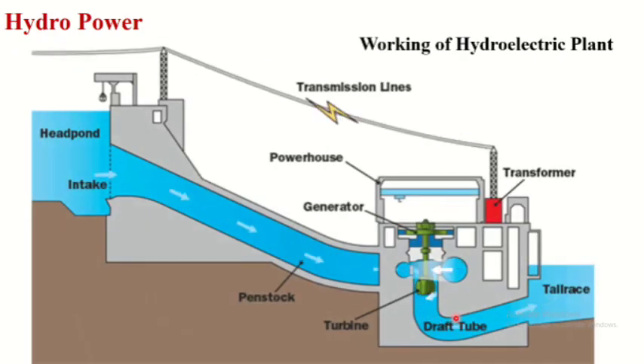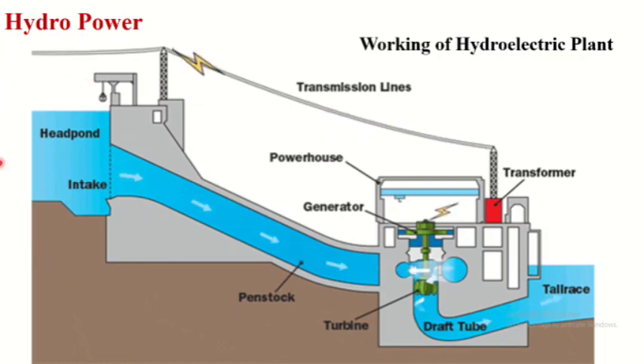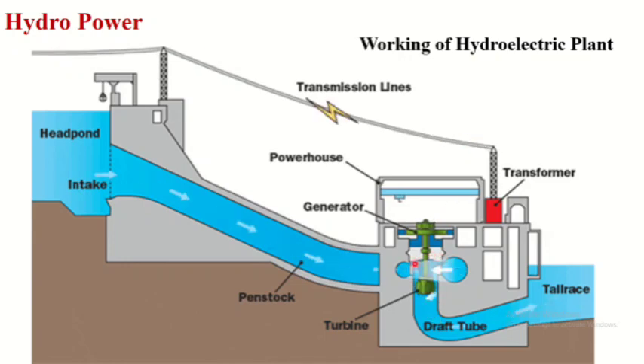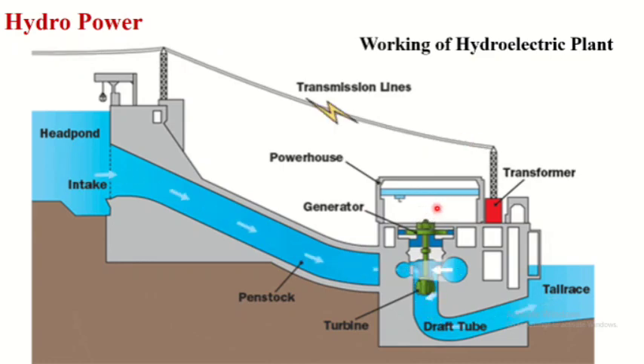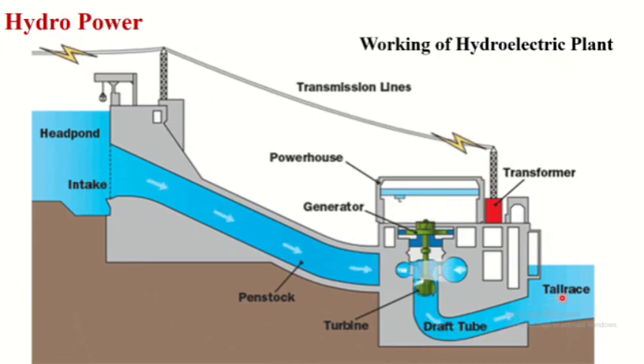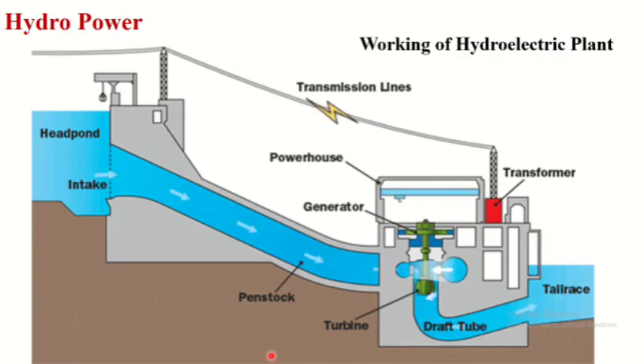Let us see the working of a hydroelectric plant. Water is collected in a catchment area during the monsoon season and stored in a large reservoir. This stored water is allowed to flow through the penstock to the powerhouse. The potential energy of the flowing water is converted into mechanical energy with the help of a hydraulic turbine. This mechanical energy is utilized to run the generator, which in turn generates electric power. This electric power is supplied to the required places with the help of a transformer and transmission lines. After coming out from the turbine, water flows through the draft tube and is fed to the river with the help of a tailrace.